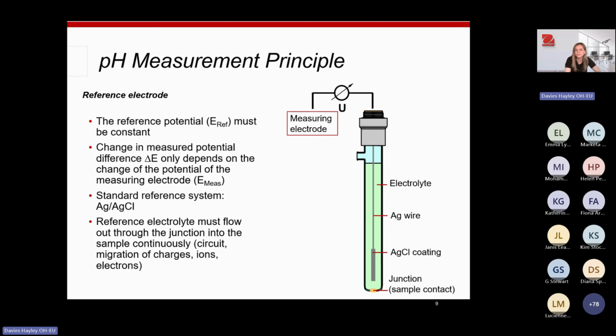Quickly look at the reference electrode. The reference electrode acts as a constant part of the sensor. It is designed to maintain a stable and unchanging electrical potential. Typically, they use a silver chloride wire, which is immersed into an electrolyte such as potassium chloride. And this electrolyte solution must be able to flow out freely from the sample junction, which is located at the tip. So it is really important to keep the reference electrode and the sample junction clean, to allow the electrolyte to flow out through the junction.